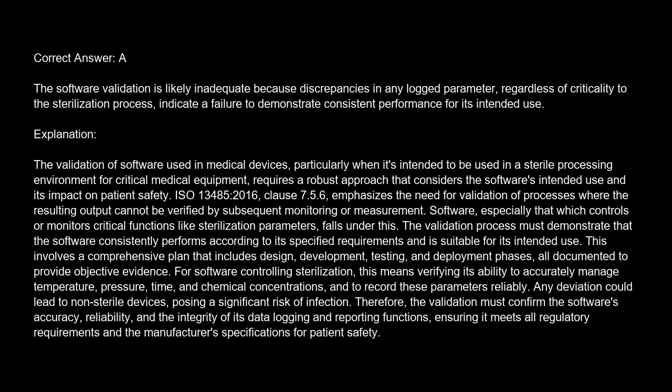be verified by subsequent monitoring or measurement. Software, especially that which controls or monitors critical functions like sterilization parameters, falls under this. The validation process must demonstrate that the software consistently performs according to its specified requirements and is suitable for its intended use.